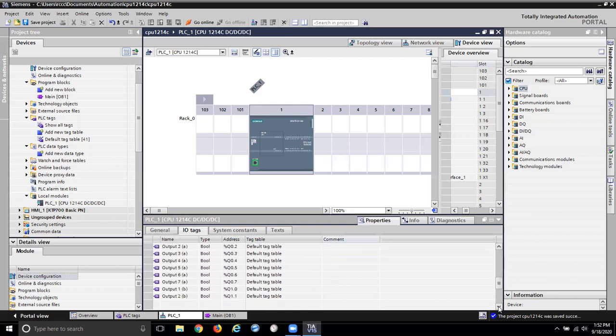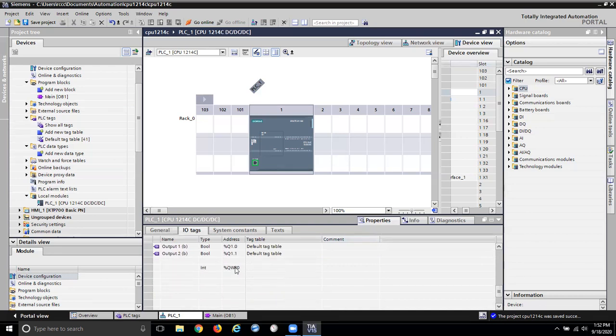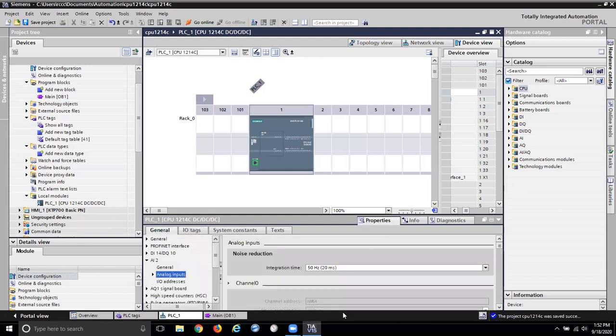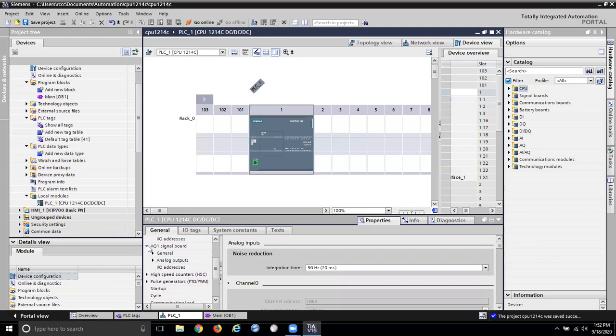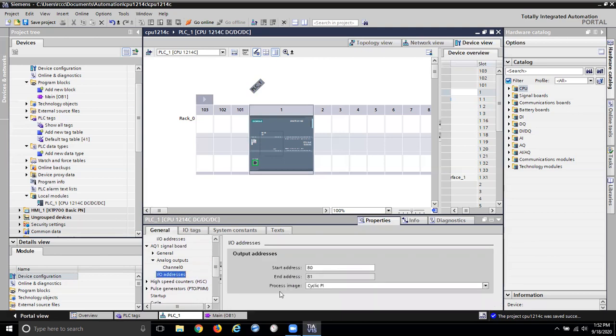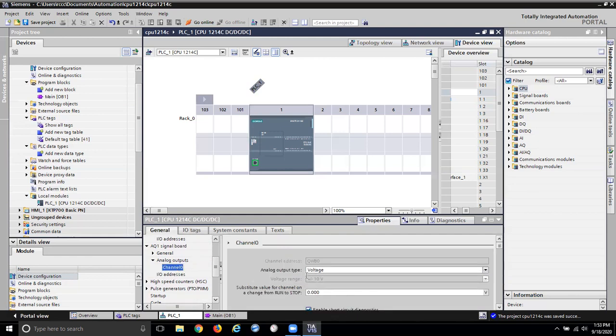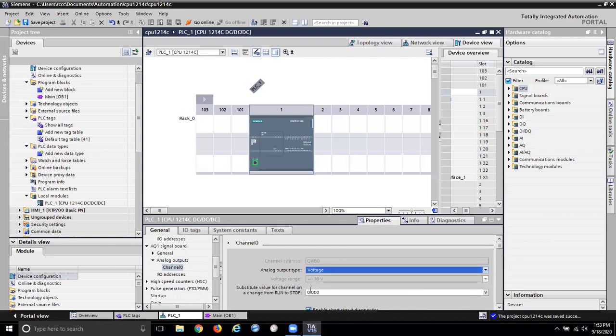Somewhere in here I've got my analog output, which I'm guessing is this one. If I go back to the general tab and scroll down, I've got an AQ1 signal board with analog output channel 0 and I/O addresses. The start address is 80, end address is 81. It is voltage — plus and minus 10 volts. This analog output type is actually configurable; I can configure it for current or voltage.